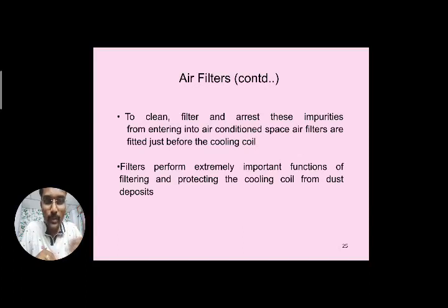So filters perform the extremely important function of filtering and protecting the cooling coil from dust deposits. What happens if the air filter is not used? All the dust will clog the cooling coil, and effective cooling is reduced, and further the refrigerant will not get vaporized in the cooling coil. Why? Because it is not making any contact with the surrounding cooling medium, so it will get completely damaged. So these air filters must be used, and service and maintenance have to be done every time.